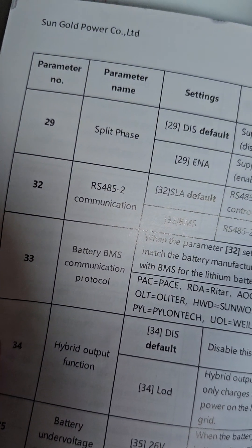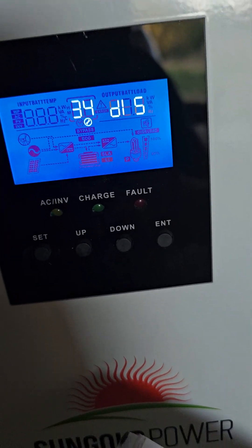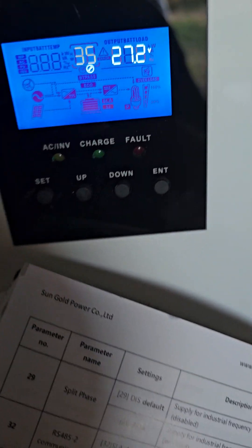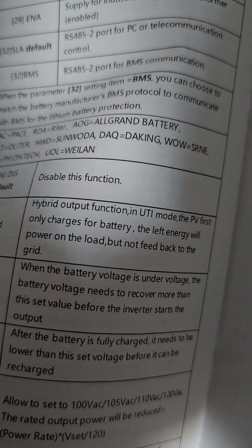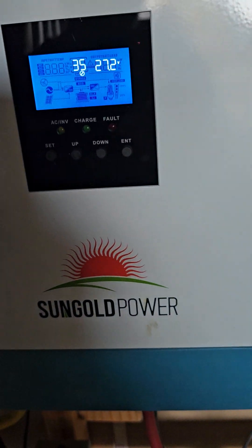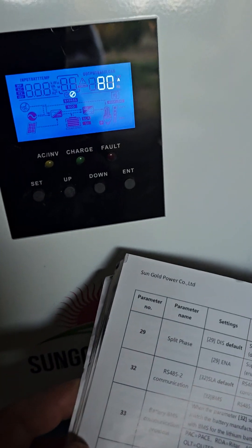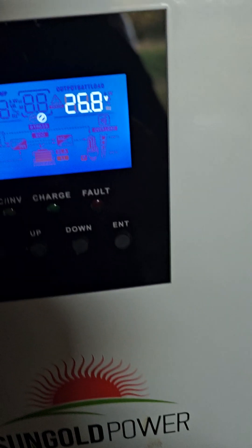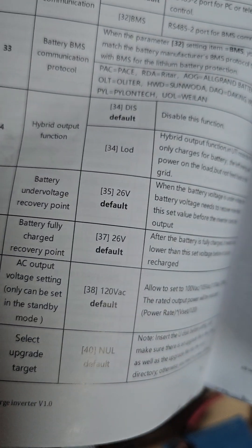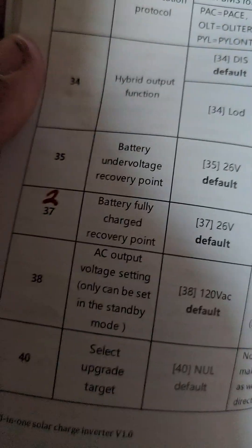Looking at parameter thirty — interestingly enough, in the book there's no thirty; it goes from twenty-nine to thirty-two. Parameter thirty-four: same as the book — disabled by default, same here. Parameter thirty-five: 26 volts in the book versus 27.2 here — so that's a change. Some of this matters because if you change the battery type from gel to lithium, some of these parameters are going to be changed automatically, as we've already seen. Parameter thirty-seven: battery fully charged recovery point — default is 26 volts in the book, but here it's 26.8. Parameter thirty-eight: 120 volts by default — same. Parameter fifty-seven: two amps — same.